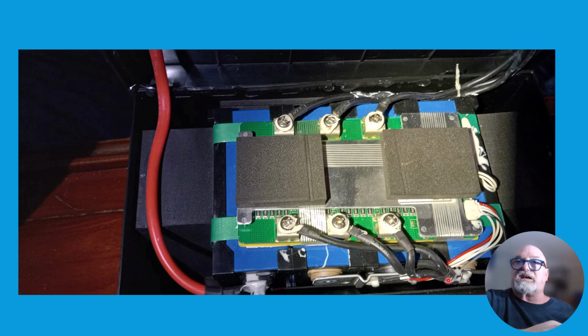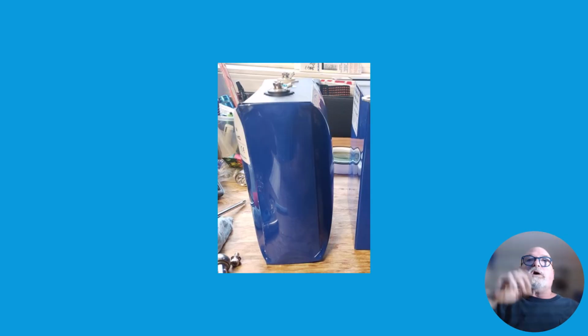It's cheesy. You'll never get a seal here if you're trying to heat shrink it. And it's just 3 10-gauge wires on a 200 amp BMS. Even though these are silicone wires, why do they use a 4-gauge over here? Because they chose not to bus these together and use an actual properly sized wire. That's why. They're cheap. So now, why do we need good construction?